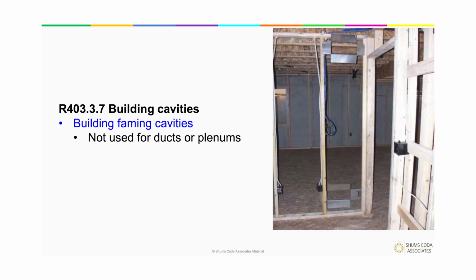It's not only how much mastic they get on there, but if there's 400,000 feet of run, it's death by 1,000 cuts. There's not just one giant hole. One giant hole is great if you can find it, but I wish it was as easy as blower doors. That's all I'm saying.